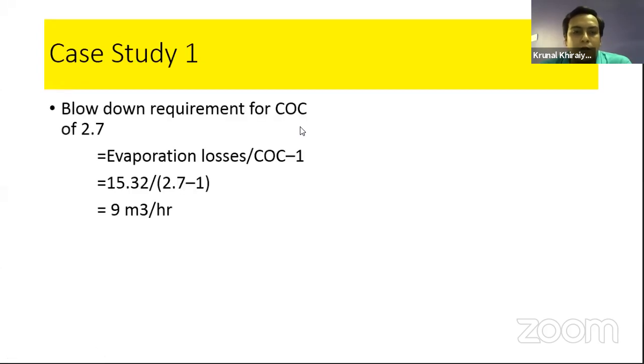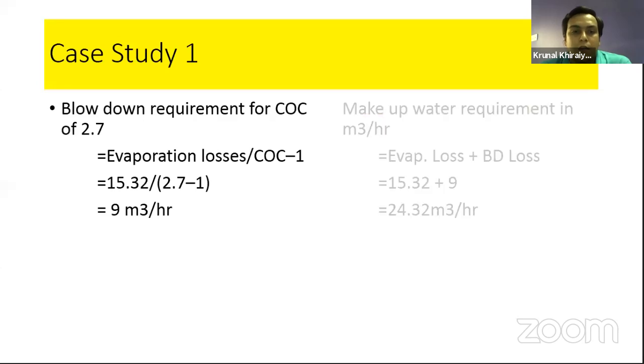Now blowdown losses means the blowdown requirement for the 2.7 COC. So evaporation losses divided by COC minus 1. Our evaporation losses come to 15.32, so it is divided by the COC, which is given as 2.7, maintained by our operation people, minus 1. So finally we get the blowdown requirement is 9 meter cube of water per hour.